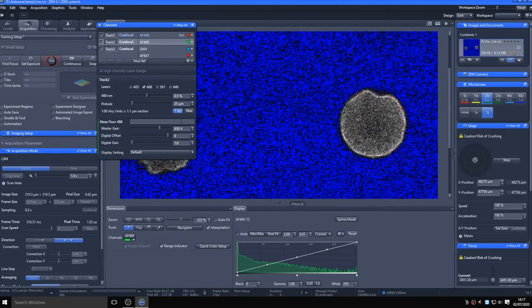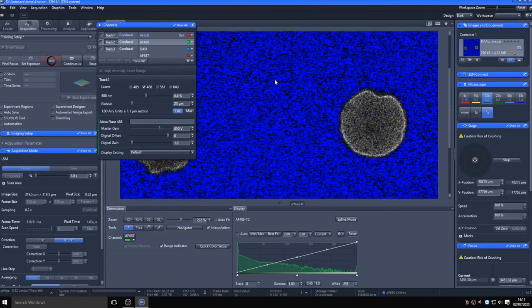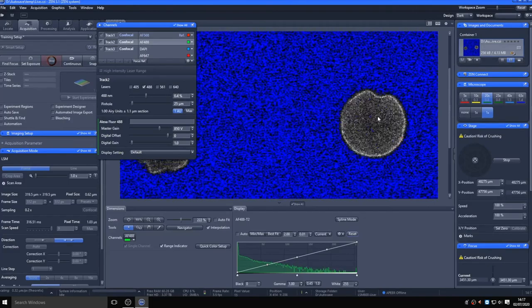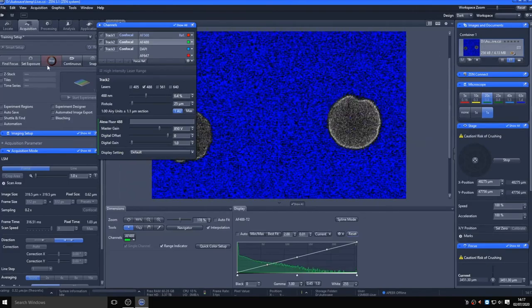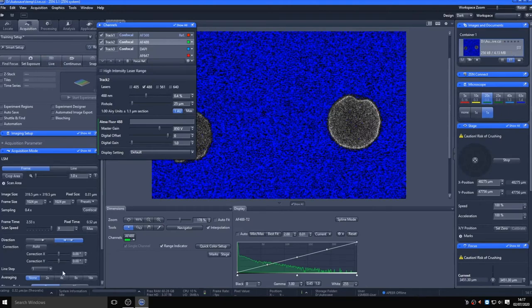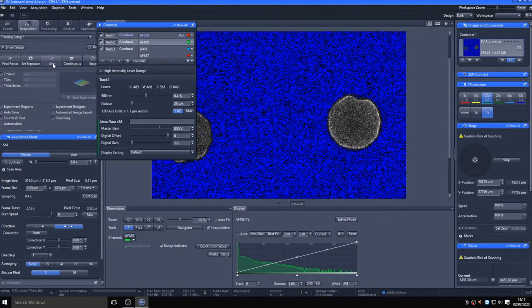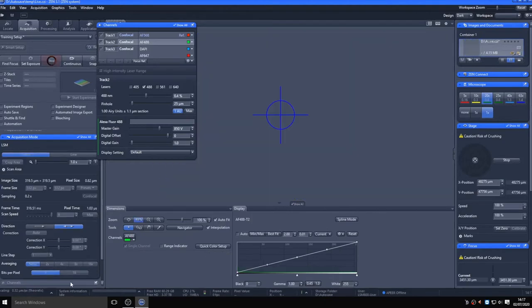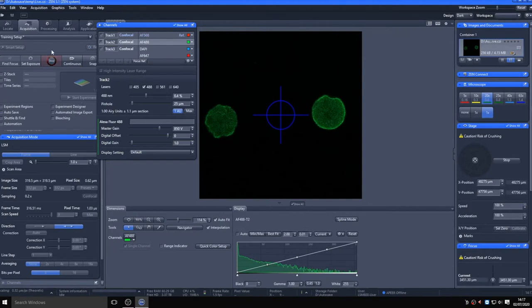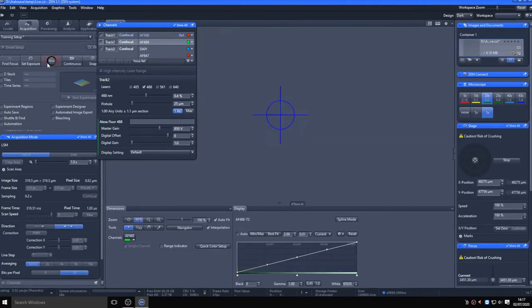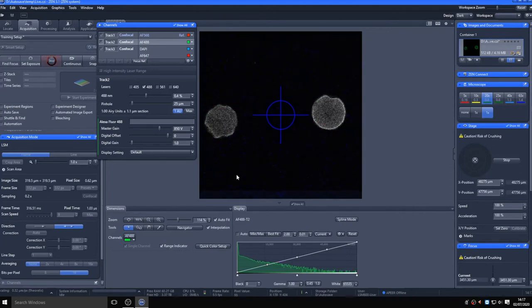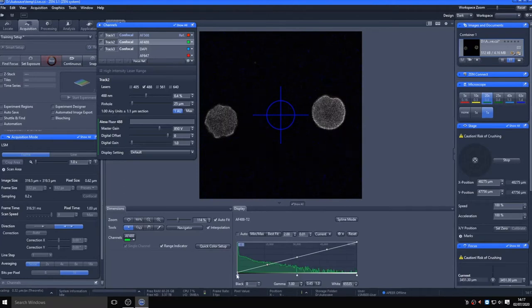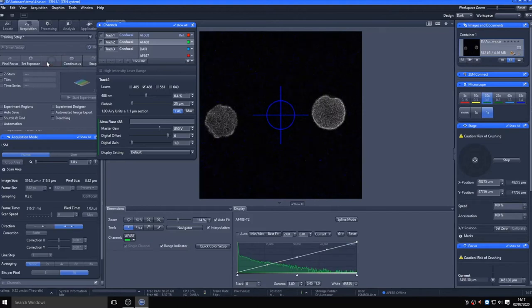It is useful to use the range indicator to detail any regions which have no signal, as shown in blue, or overexposed as shown in red. Though be careful, as in some versions of Zen, the lookup table minima and maxima are applied to this indicator, so ensure you have the lookup table reset to full range. Usually, I switch the output to 16-bit mode to increase the gradation between black and white from 256 levels to 65,536. This does not increase the dynamic range, so overexposed pixels will still be overexposed in 16-bit mode. You often do see a decrease in the apparent underexposed signal, as shown by the reduction of the blue background, which is due to the larger dynamic range that data can be binned to from the detector.